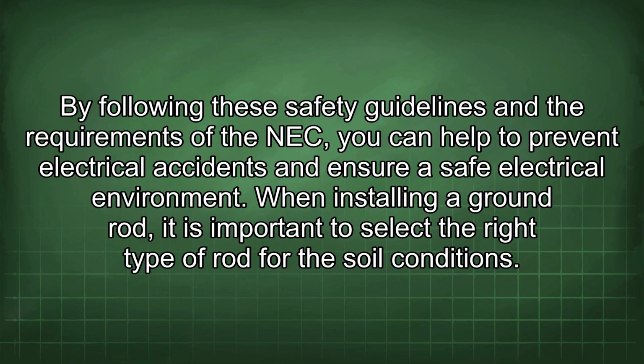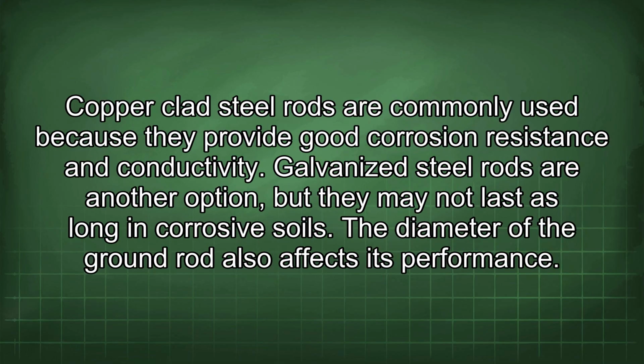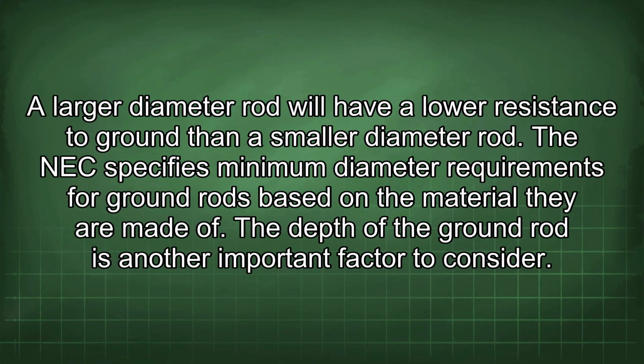When installing a ground rod, it is important to select the right type of rod for the soil conditions. Copper-clad steel rods are commonly used because they provide good corrosion resistance and conductivity. Galvanized steel rods are another option, but they may not last as long in corrosive soils. The diameter of the ground rod also affects its performance. A larger diameter rod will have a lower resistance to ground than a smaller diameter rod. The NEC specifies minimum diameter requirements for ground rods based on the material they are made of.